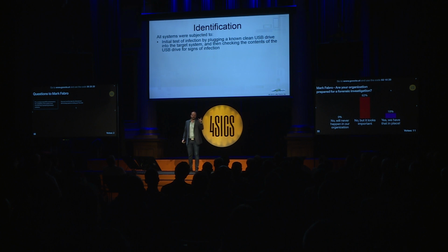So we created this naming convention. Across all those 30 assets in a production environment with 2 teams spread over 2 different sites, every single system was going to be subjected to the initial test of infection by USB. And again, in a second we're going to get down into the mechanics of Hamweq and how it actually moved. So every single possible machine was tested by the insertion of a native, clean USB stick to see if the malware would actually move, and then analysis of that malware to determine if it has been modified based on the specifics of the control system component it had actually infected.